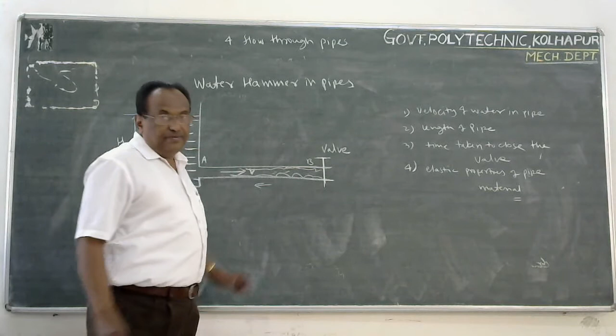Now, when the water is flowing with a certain velocity, and if you suddenly close the valve, what will happen? The momentum of the flowing water, the water which is flowing at very high velocity, is stopped suddenly by closing this valve. The momentum of water will be disturbed, and reverse pressure waves will be transmitted from this point in the reverse direction of the flow along the pipe.